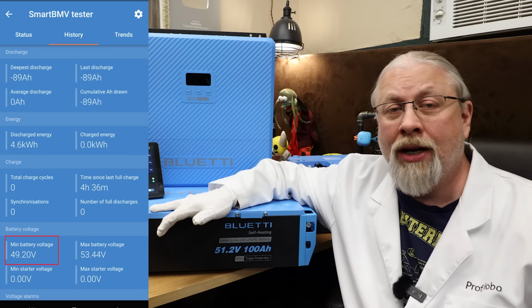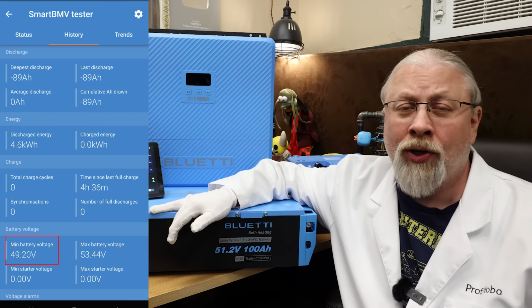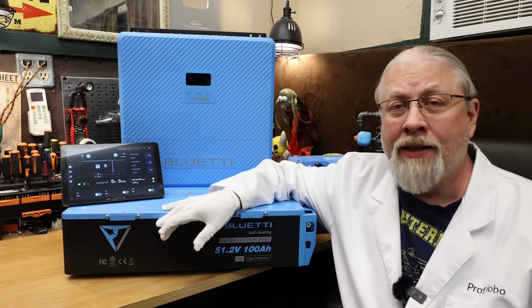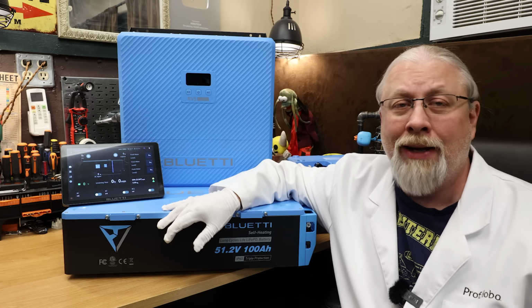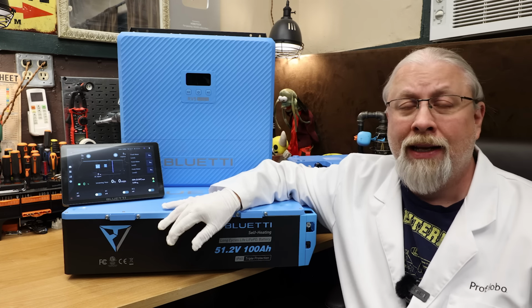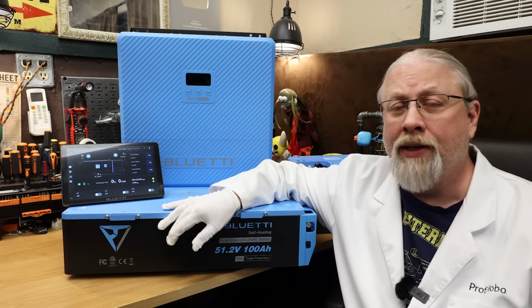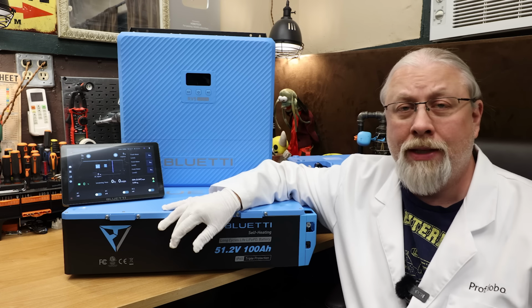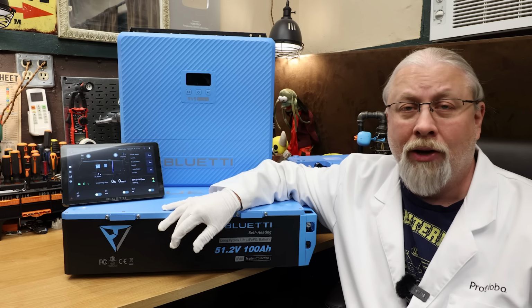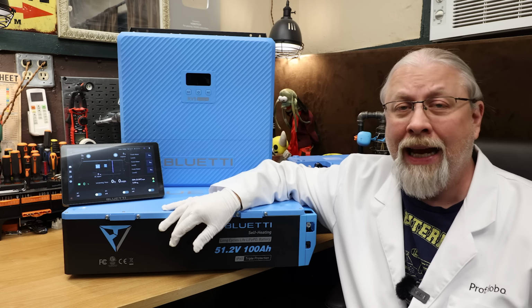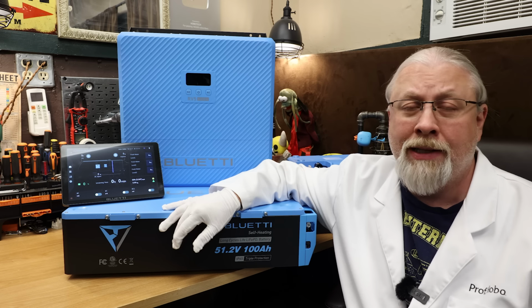Note that in the screenshot of the Victron results, it only discharged down to 49.2 volts. This tells me they're only using about the center 80% or so of the battery, and that is probably already oversized. But in any case, those are the results of the best 2 runs, and oversized or not, you're only getting about 89% of the available capacity of the battery.